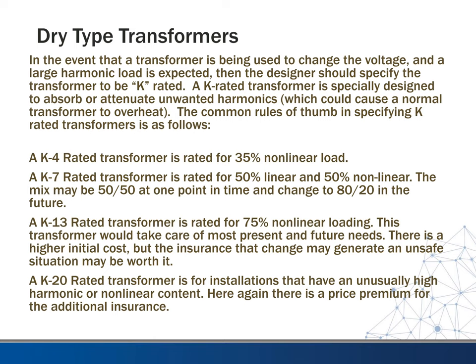If you use a K4 rated transformer, you're expecting 35% of your load to be nonlinear, and again, computers can be nonlinear loads, fluorescent lighting can be nonlinear. A K7 rated transformer is rated for 50% linear, 50% nonlinear. So if you think half your loads are going to be nonlinear, you might want to go with the K7. A K13 rated transformer is rated for 75% nonlinear loading. So again, this would take care of a lot of that. And then finally, a K20 rated transformer is for installations that have an unusually high harmonic or nonlinear content.